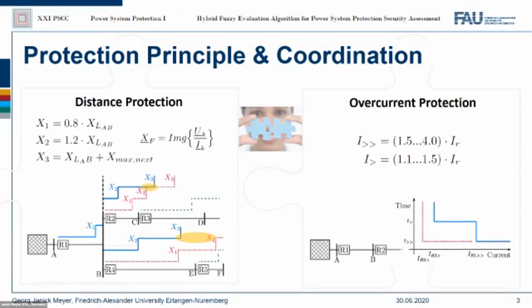In the shown grading chart on the left side for a radial network, different zone lengths for distance protection relay R1 are shown. It can be seen that using standard equations to calculate the zone lengths, the zone reach of X3 of relay R1 is overlapping with X3 of relay R2. So that could cause an overfunction. At the lower line, the zone reach X3 of relay R1 is too short. So relay R4 has no backup protection, which could cause an underfunction.